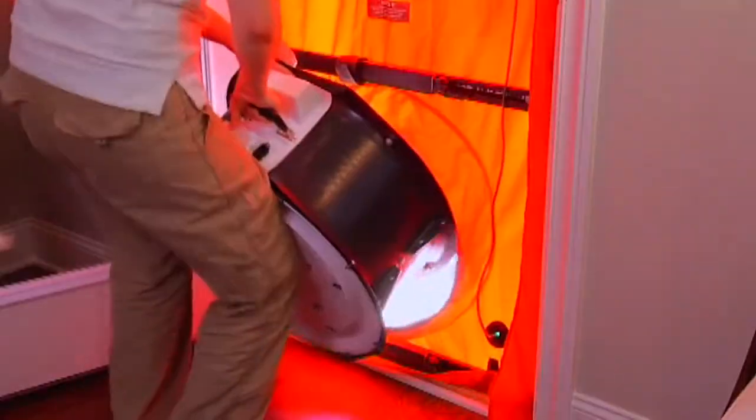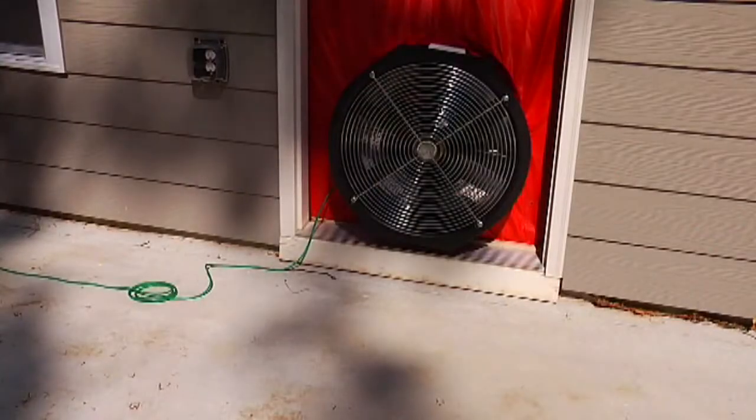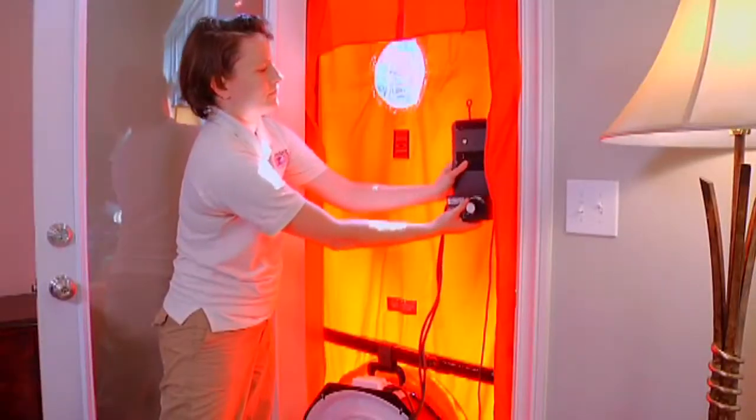to actually come on and be the lungs of the house. When we go through and do all this air sealing, we're actually going to do what's called a blower door test afterwards, and we're going to see how much the air is changing over in the house. Based on the number of inhabitants and some other details of the house, we know how much fresh air needs to be going through this house to make sure it stays healthy. So by air sealing the house as tight as we can, we don't have to worry about the ventilation concerns of air coming through around your windows, around the baseboards, up and through your ceiling.